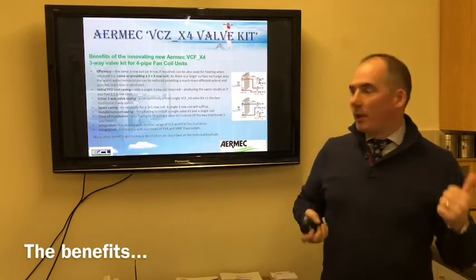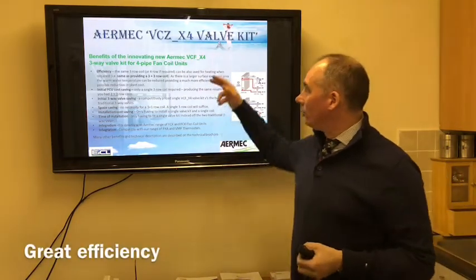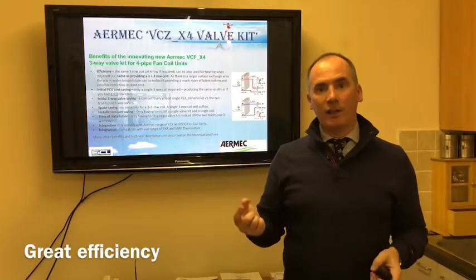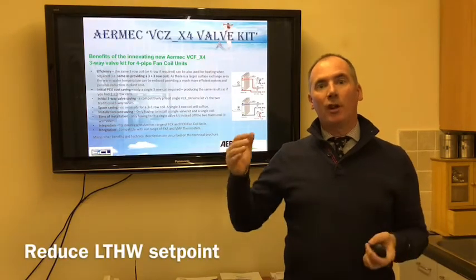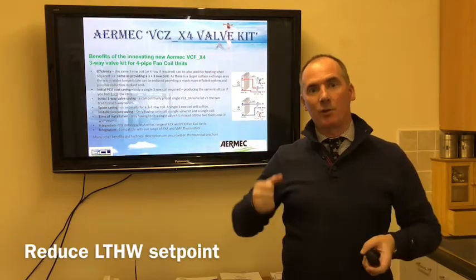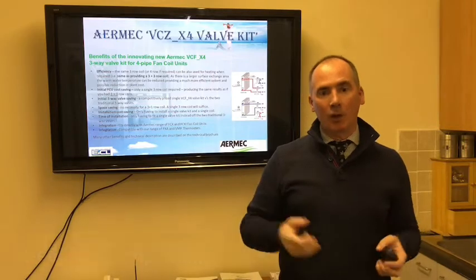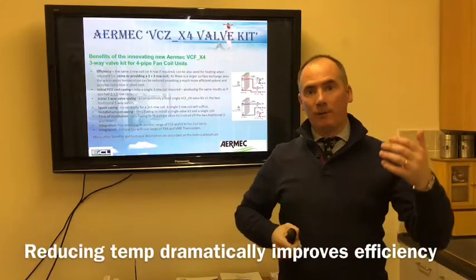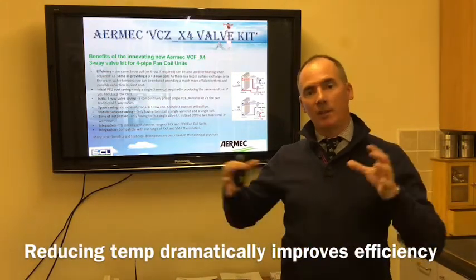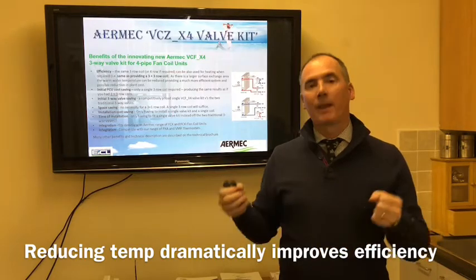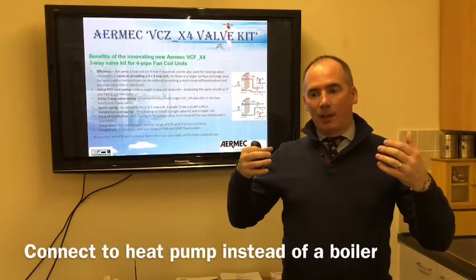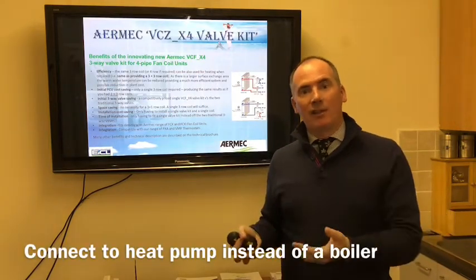So what are the benefits? Okay, straight away, like I said, the efficiency, 3 rows instead of 1 on the heating. So what can you do? You can obviously reduce the warm water temperature. So instead of taking 60, 65 from a boiler, you can now use maybe 35, 40, 45, something like that, obviously depending upon the sizing of your fan coil. And you don't even necessarily need to connect it to a boiler anymore.